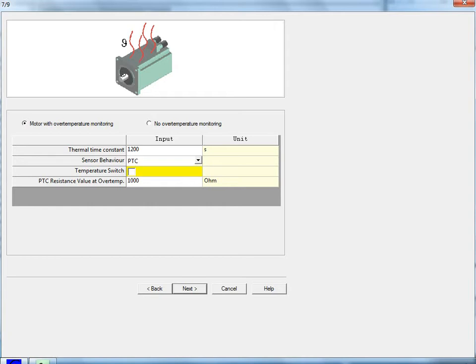The sensor can be either PTC, which is a positive thermal coefficient, or an NTC type. For PTC, you input the resistance at the over-temperature. If it's only a switch, check the box. If this is based on a standard Parker motor, you do not need to change this. Go ahead and click Next.